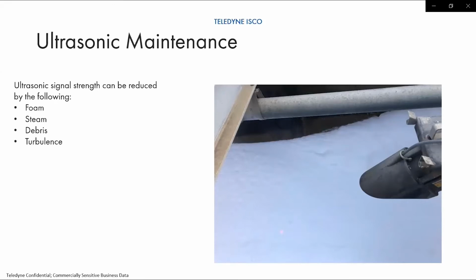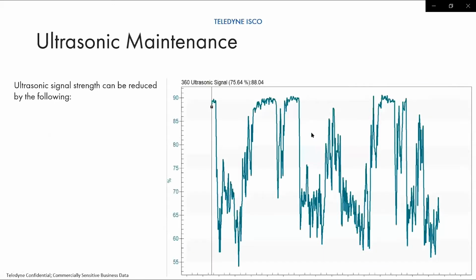Now, one thing you could do, if you start seeing ultrasonic signals going all over the place like this, is test your sensor by putting a board or something across your flume. In this case, it's changing quite rapidly. After an hour, I would expect my signal strength to remain consistent, high in the 90% range, and the level to remain consistent. If it keeps moving around like this, even when you're shooting at a solid target, then you have a problem with that sensor. Some sensors have ceramic plates in there that are used to transmit the signal, and if they crack, it creates noise, which could result in something like this.